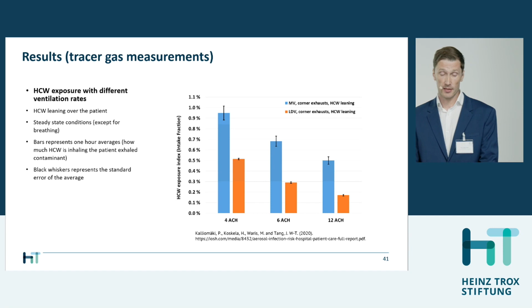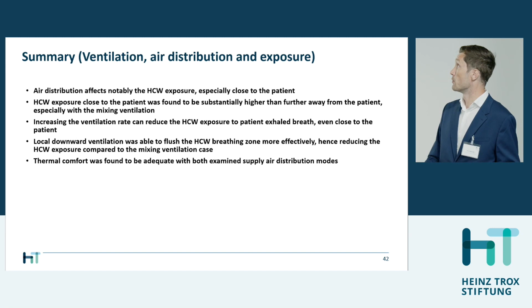So, a short summary about this ventilation, air distribution and exposure part. The air distribution affects notably the healthcare worker exposure, especially close to the patient. Healthcare worker exposure close to the patient was found to be substantially higher than further away from the patient, especially with the mixing ventilation. Increasing the ventilation rate can reduce the healthcare worker exposure to the patient exhaled breath, even close to the patient. However, local downward ventilation was able to flush the healthcare worker breathing zone much more effectively, and hence reduce the healthcare worker exposure compared to the mixing ventilation case notably. And also the thermal comfort was found to be adequate with both examined supply air distribution modes.